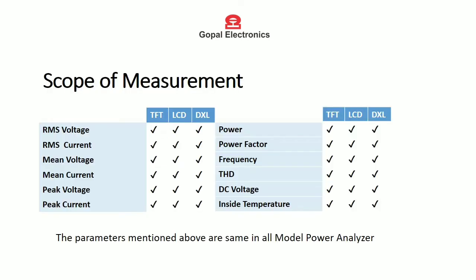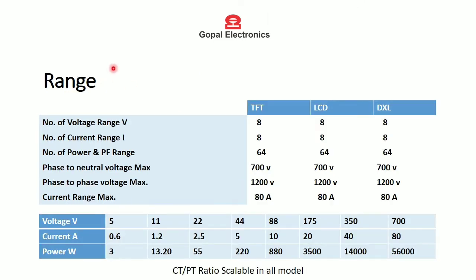In scope of measurement, the parameters mentioned in the table can be measured by all models. The range of all models is the same: there are 8 ranges of voltage, 8 ranges of current, and a total of 64 ranges of power and power factor. Phase-to-neutral maximum voltage is 700 volts, phase-to-phase maximum voltage is 1200 volts.